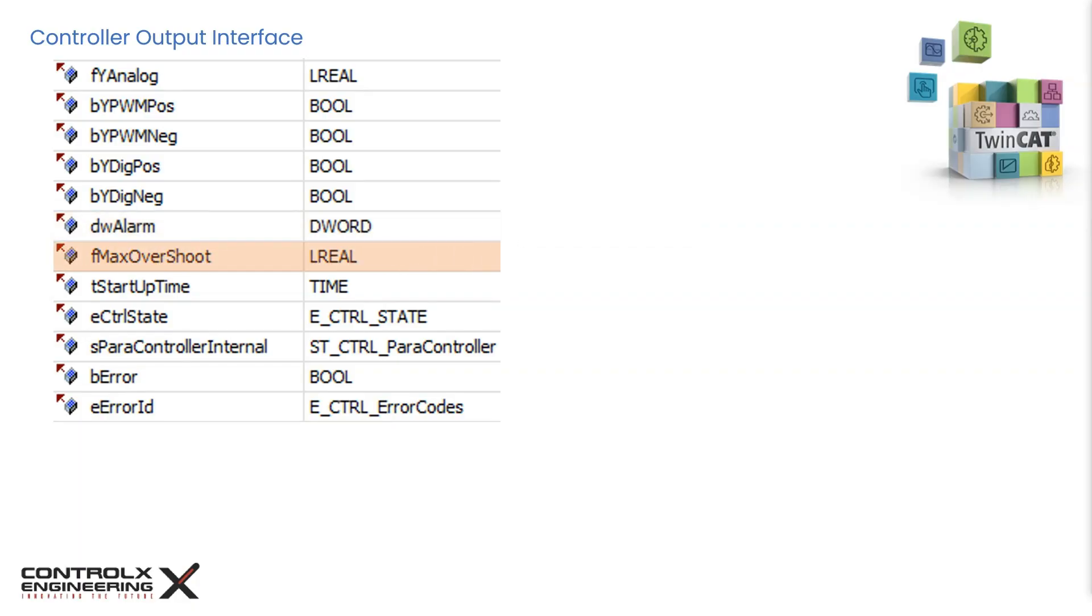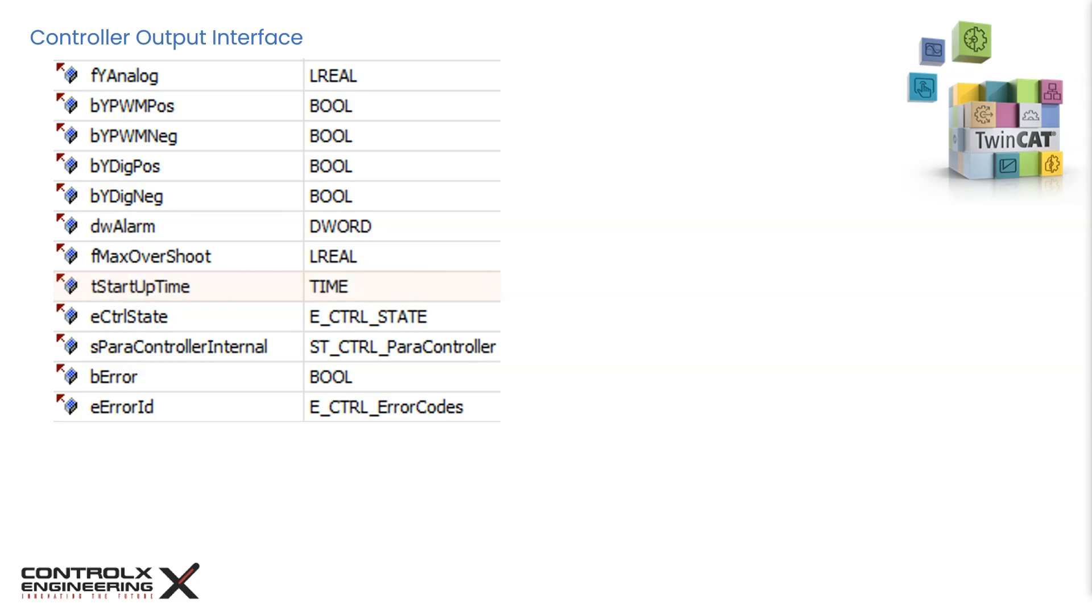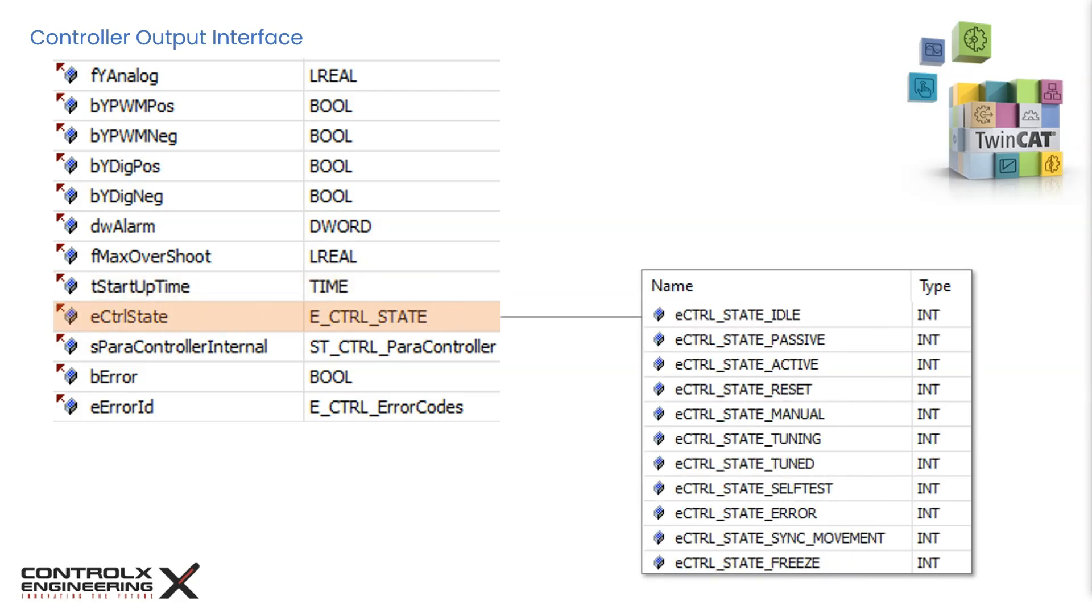When a new setpoint is entered, the controller sets its output to get the process value to reach the set temperature. As in the case with PID control, there is always some overshoot after which the control value corrects itself. This output records the maximum overshoot. This is the amount of time it takes for the process value to reach the desired setpoint. Every time a new setpoint is entered, this output will update the startup time. This output indicates the current state of the controller. The state can be set using the e-control mode input that we discussed earlier. Once the input has been accepted, the output mode is updated to reflect the current state of the controller.